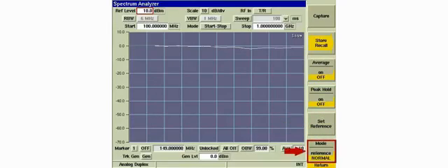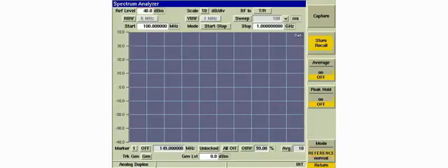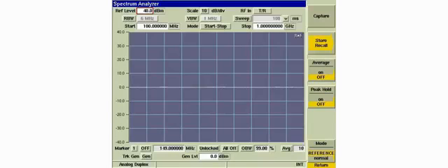Once the trace is stored as the reference, pressing the mode soft key will toggle the analyzer to the reference mode. When the analyzer is in the reference mode, the reference trace data points are all translated to 0 dBm.